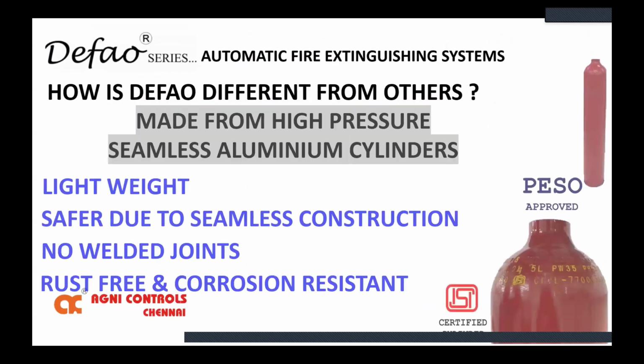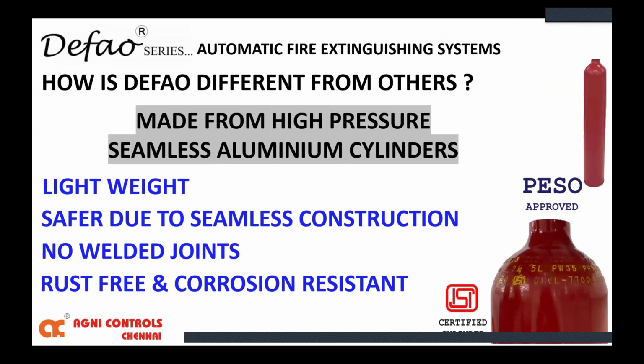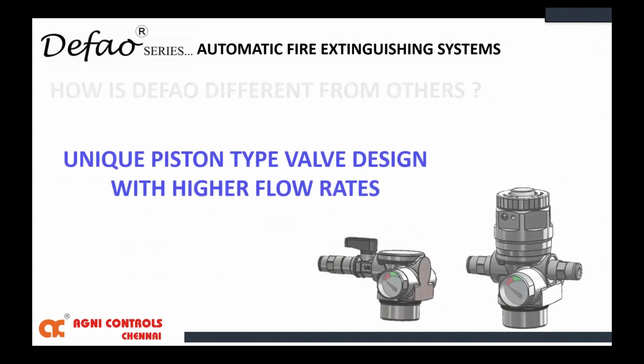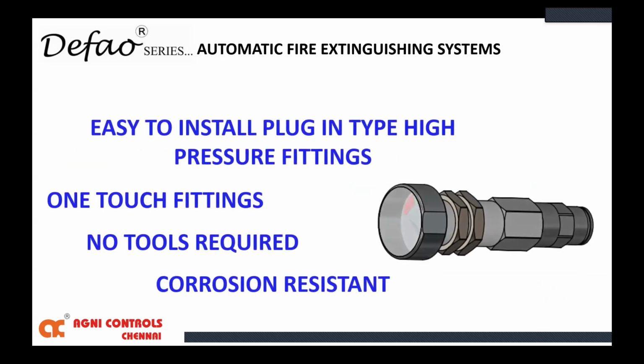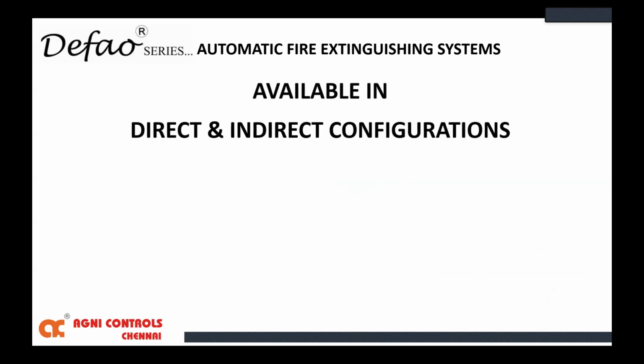So how is the Defao different from others? Many of the tubing systems use welded cylinders. These are aluminum seamless ISI marked, PESO approved cylinders with a unique piston type valve with higher flow rates, so more agent is discharged through these valves. Easy to install plug-in high pressure fittings. No special tools are required, just plug-in type compression fittings. Available in both direct and indirect configurations.